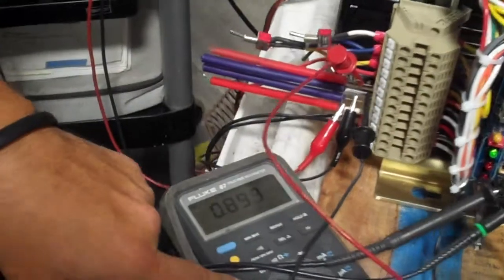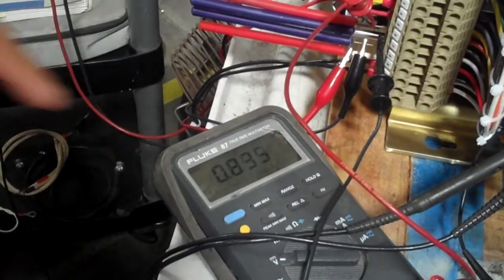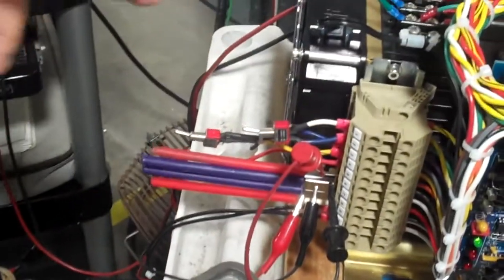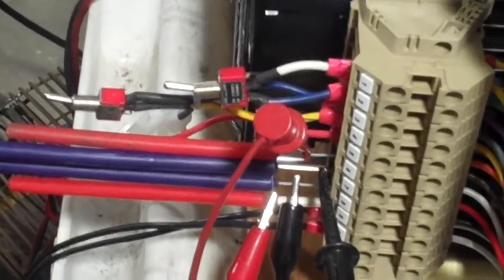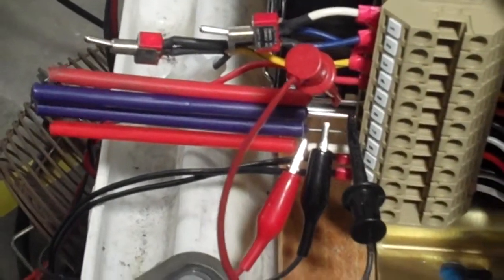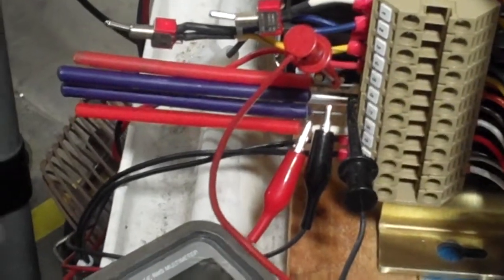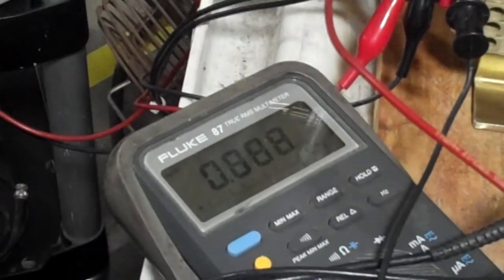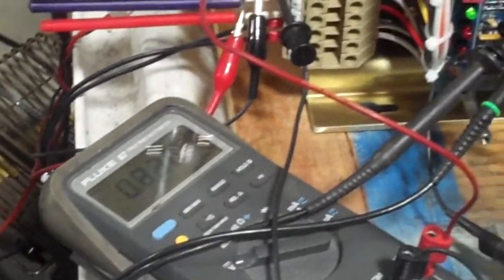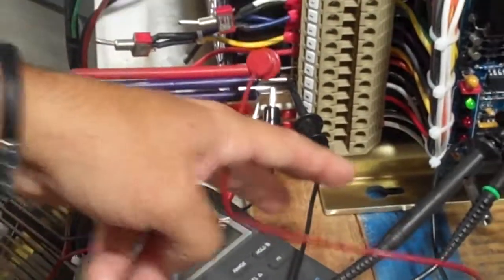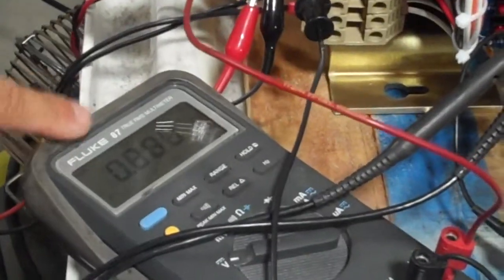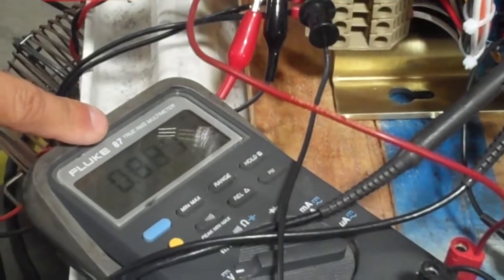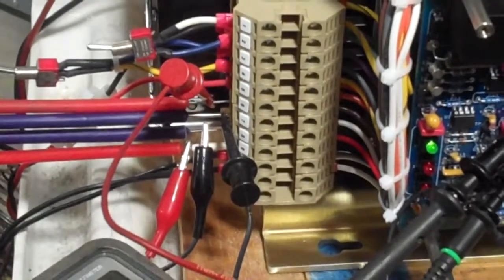Now, in your email, the question is, what's going on with 7 and 8? I have a meter between 7 and 8, and I'm recording voltage. Remember, one side is 30 volts, the other side is the side that when a current trip condition exists, there will be a path to ground, so that if this is a relay, you have the relay energizing or de-energizing. So right now you notice if you had a relay between 7 and 8, the relay will be de-energized because you only have 0.8 of a volt. It will not be enough for the coil to engage.